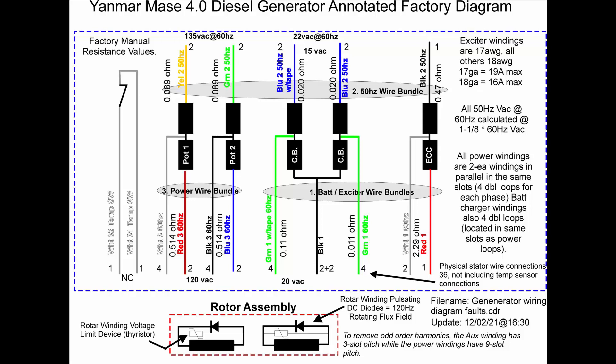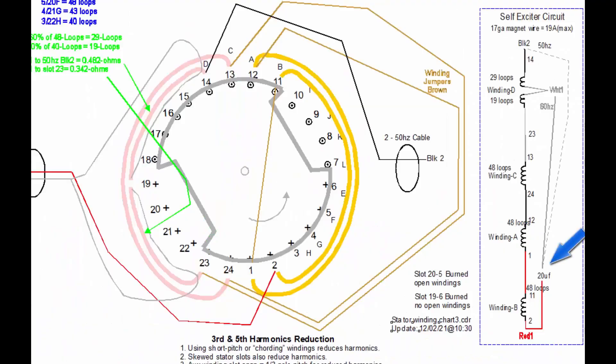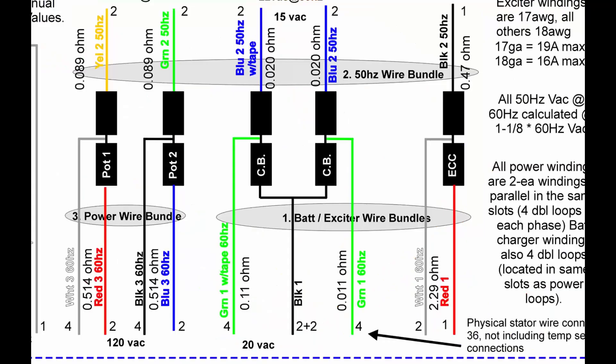This generator is unique in several ways. The first way is that it's a self-excited generator. There's no brushes, there's no slip rings, nothing. The way it works is it has a capacitor across the exciter winding and that builds on the residual magnetic fields left in the iron core when you start up the generator.